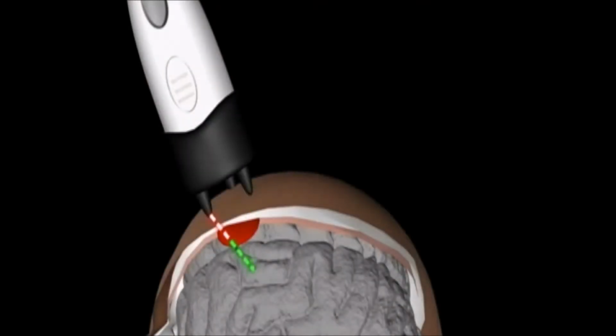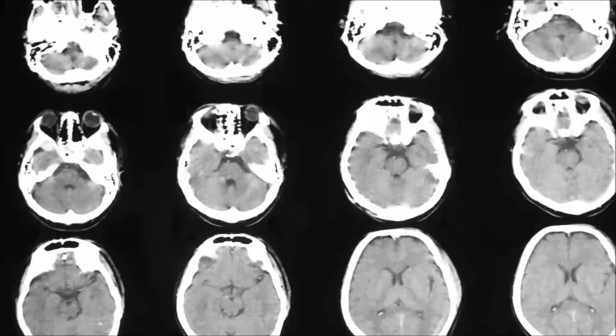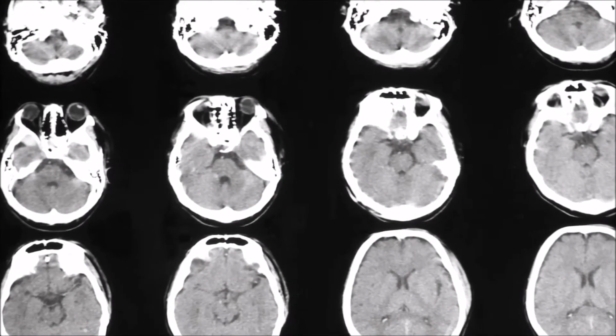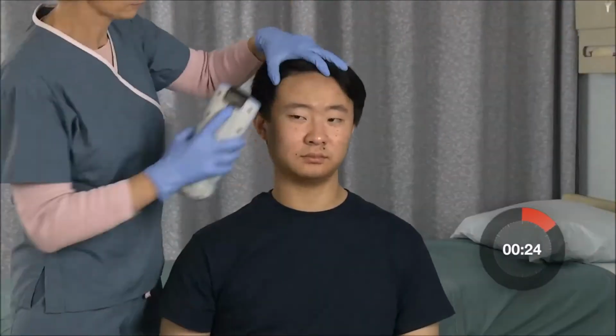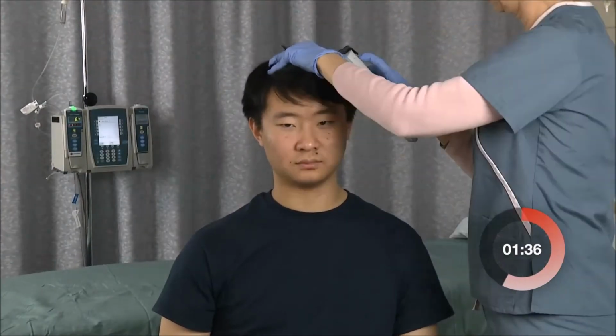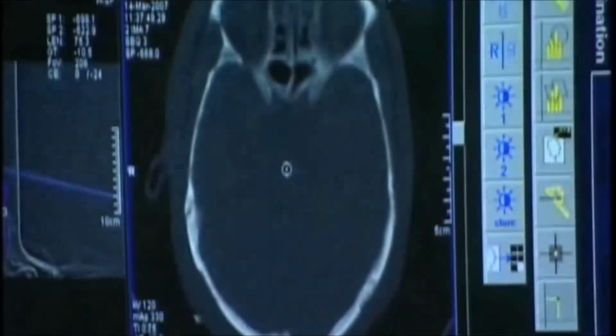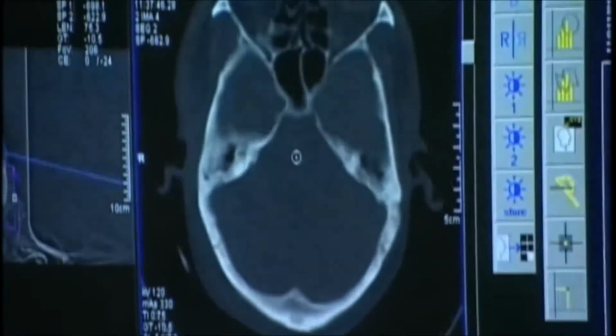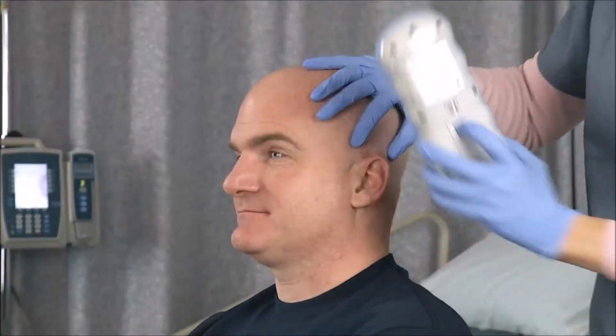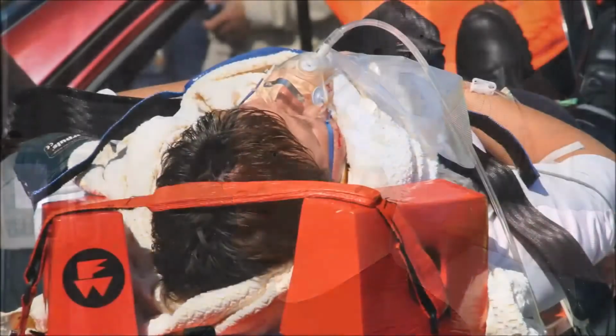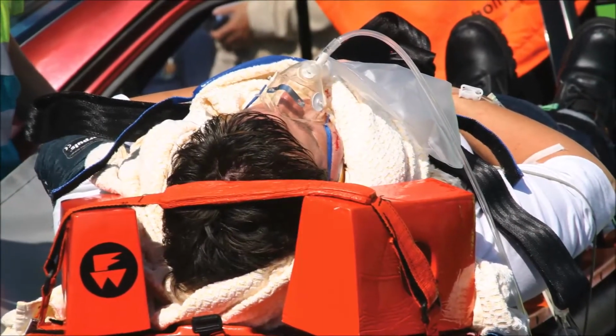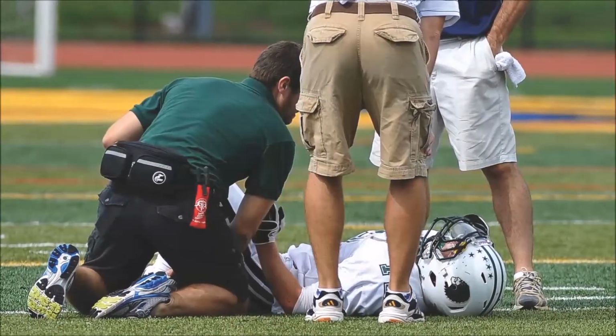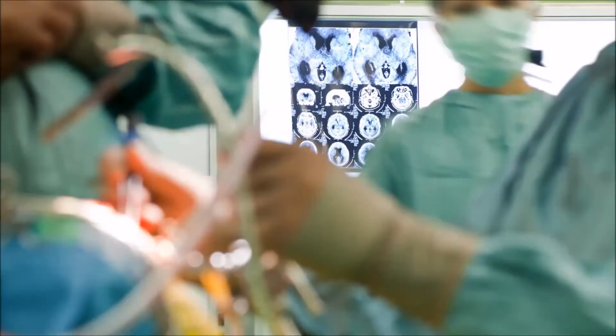The detection depth is superficial, within 3.5 centimeters of the skin surface, where blood typically migrates in most cases of bleeding. Patient measurement is typically completed within 2 to 3 minutes per scan, and the device can detect hematomas greater than 3.5 milliliters in volume. The Infrascanner is not a replacement for a CT scan. It is a simple, easy-to-use screening tool that can be used to identify high-risk patients requiring prioritization for CT scanning and neurosurgical treatment.